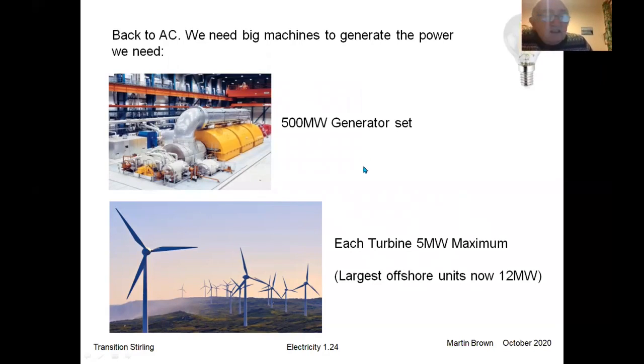However, of course, the trend now is to have distributed smaller generating systems like these wind turbines. Wind turbine sizes have been growing steadily over the last 20 years. Typical onshore wind turbines that you'll see around Scotland are 5 megawatts maximum, or they might be 3.5 megawatts. It's this kind of size, and they're still pretty big when you get close up to them. And remember, this is the maximum that you get. If the wind blows too much, or if it's blowing too little, you get less than the maximum power. You typically get somewhere between 20 and 30% off a wind turbine on average. So if you've got a 5 megawatt wind turbine, averaged over the year the power you'll get off it might be something like a megawatt and a half.